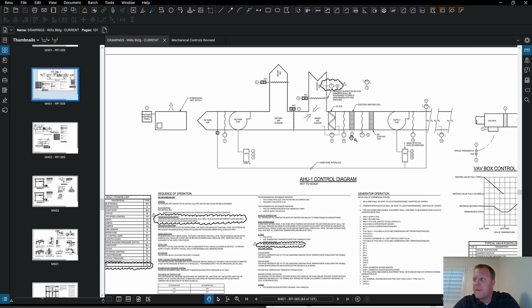I don't know if the right word I'm using might make sense. A demand. Does that word make more sense? There needs to be a demand for whatever it is trying to accomplish. So if it's the hottest part of the year and we're trying to say this is not an electric heating coil, we're still talking about it being a boiler water heating coil, and the air handler is trying to cool everything down, there's not much of a demand for boiler water. So it's hard to get that boiler started up and running correctly without much of a demand.